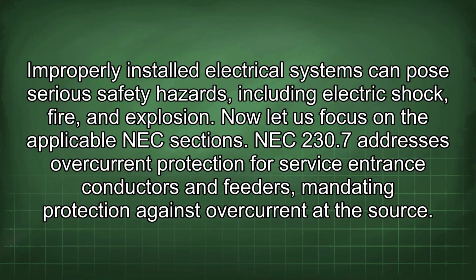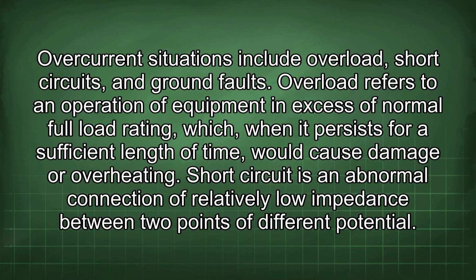Now let us focus on the applicable NEC sections. NEC 230.7 addresses overcurrent protection for service entrance conductors and feeders, mandating protection against overcurrent at the source. Overcurrent situations include overload, short circuits, and ground faults. Overload refers to an operation of equipment in excess of normal full load rating, which, when it persists for a sufficient length of time, would cause damage or overheating.